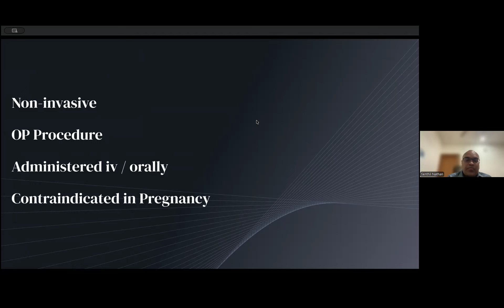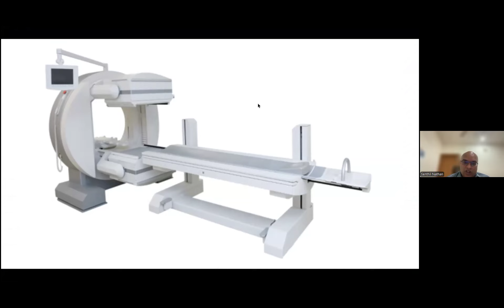Let me start with the gamma camera. This is how a gamma camera looks like. This is a dual head gamma camera. This is one head and this is the other head. This is a radiation detecting machine and not a radiation producing machine. So what we do, we administer the appropriate radioisotopes or radiopharmaceuticals intravenously. The patient will become a radioactive source, and those gamma rays emanating from inside the patient will hit the camera and produce an image. That's how it is done.